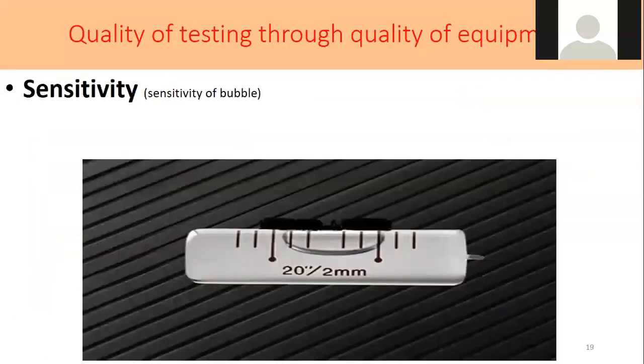The resolution and the sensitivity are two important aspects of any good machine. As we know, we use the bubble in surveying equipment. How many of us, in our whole testing career, have officially checked the sensitivity of the bubble? How many of us have calibration records for the sensitivity of the bubble? If the bubble is disturbed by a couple of centimeters, or even 5 millimeters, all the sensitivity of the machine is lost. So whatever accuracy it has on the staff, if the survey instrument's bubble, resolution and sensitivity are not maintained, what is the use of such equipment? So when using such machines, we need to check their sensitivity.